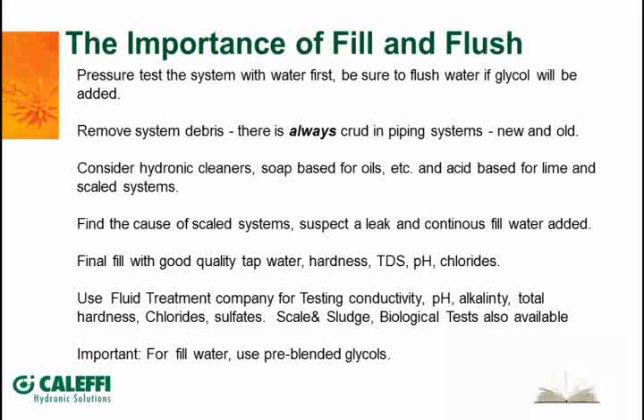And even on a small copper system that you're doing, you should be reaming your pipe with maybe a pencil reamer. I know a lot of guys nowadays are cutting their copper with chop saws or those little portaband saws, like a little band saw, and that's going to leave shavings inside there. You want to get that stuff out. But the other thing you're going to find inside there is all different components that they use in the manufacturing and the assembly of the boilers and pumps when they put them together. There's different lubes that they use to put seals in. If they threaded any pipe, there might be some cutting oil or something, residue inside the equipment. So all that needs to get out.